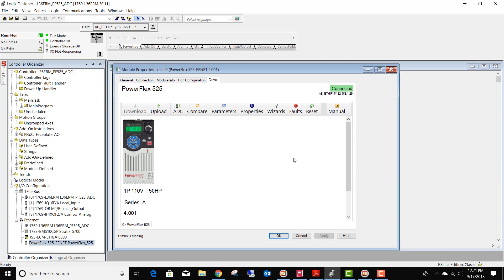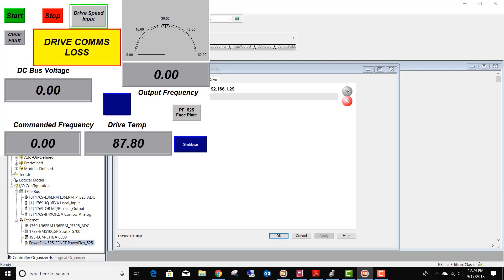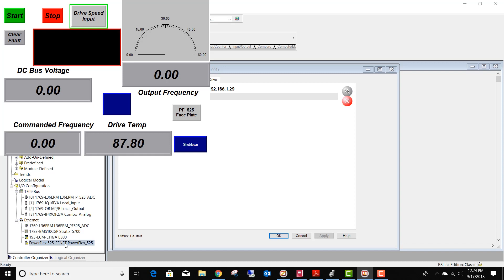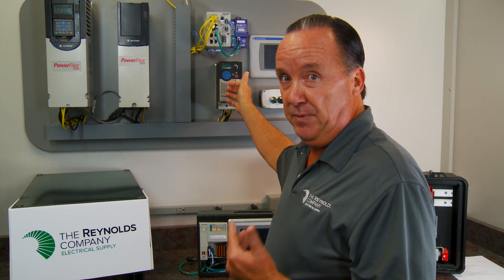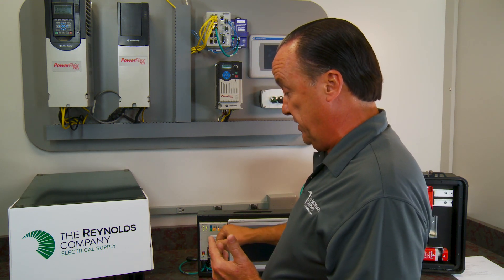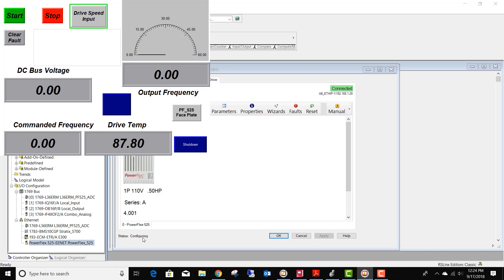We'll take this file and download it to the controller. So, let's remember our scenario: our PowerFlex 525 drive has failed. You can see we've lost our drive — the PowerFlex 525 has our yellow triangle of death, and it says faulted. We've gone into stores and got another one, replaced it, plugged it in, and made all the necessary connections. Now the controller is trying to connect to the drive but can't because it doesn't have an IP address. The Stratix 5700 managed switch notices this device is requesting an IP address and gives it its IP address. The controller then notices a difference between the configuration files stored here and what exists on the drive. So now we're configuring the drive — the controller sends the set of configuration files, and there it just sent it. Now you see it say running, and the yellow triangle of death is gone. We now have full control of our drive.